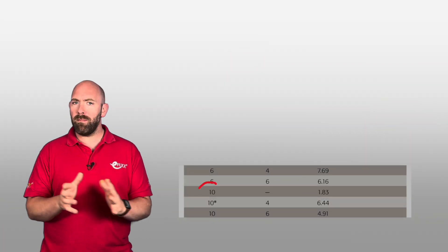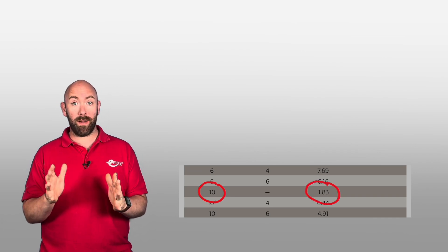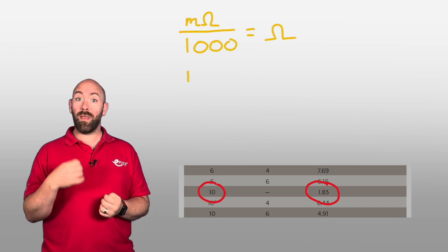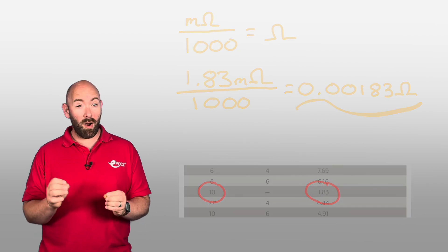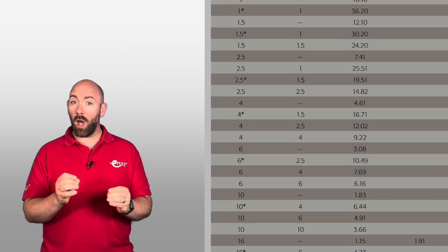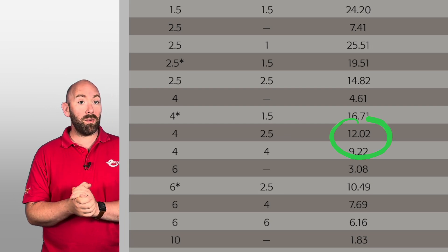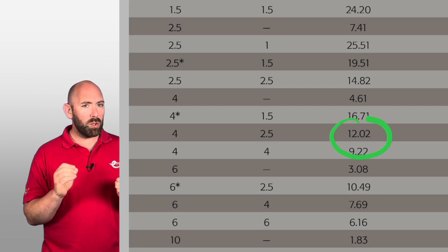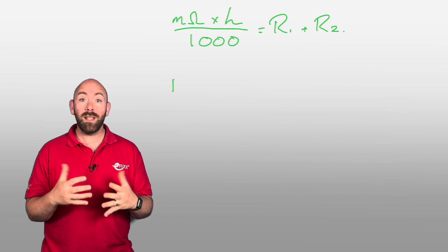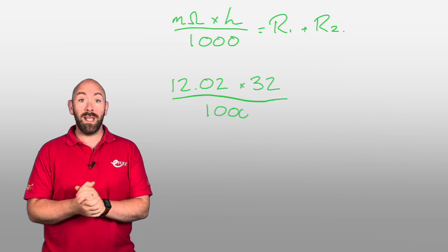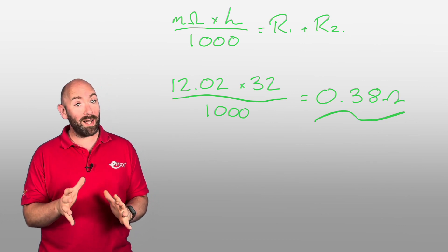For example, this 10 millimetre squared cable has a resistance of 1.83 milliohms per metre. If I divide this by a thousand — as we have a thousand milliohms to the ohm — it gives a value of 0.00183 ohms. For our circuit, a 4 millimetre line conductor with a 2.5 millimetre squared protective conductor has a resistance of 12.02 milliohms per metre. We multiply this by the length of 32 metres, then divide by a thousand, giving us an answer of 0.38 ohms — our expected R1 plus R2.